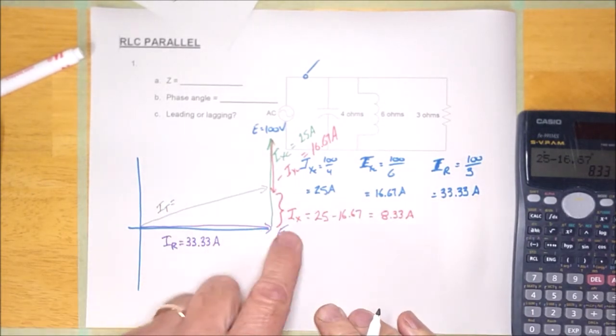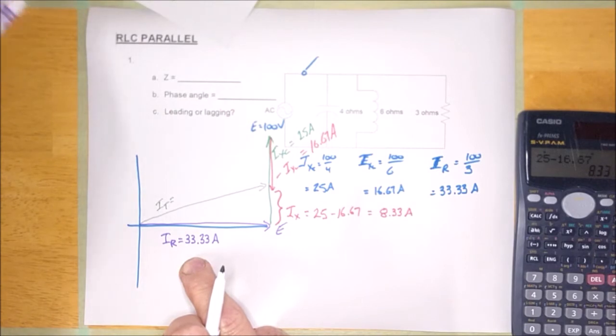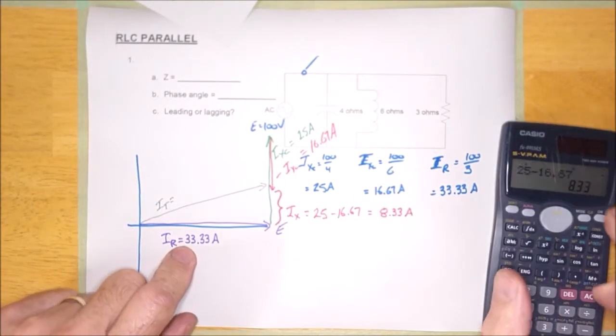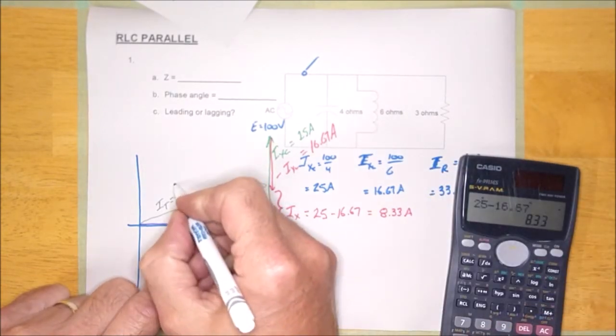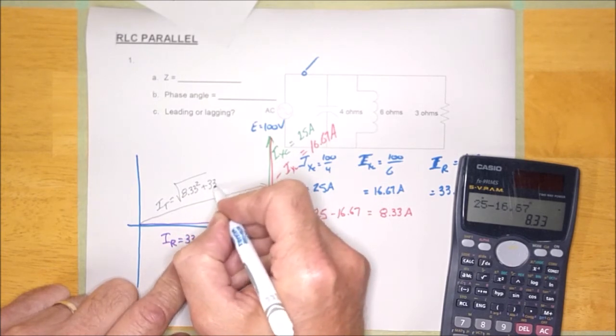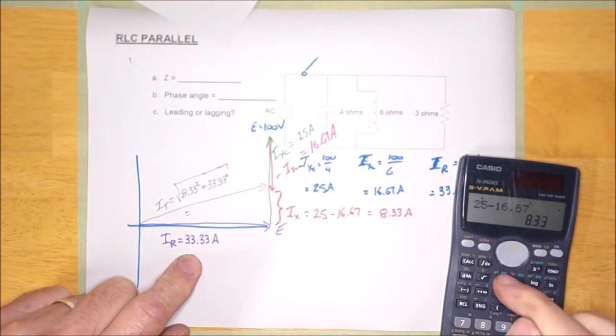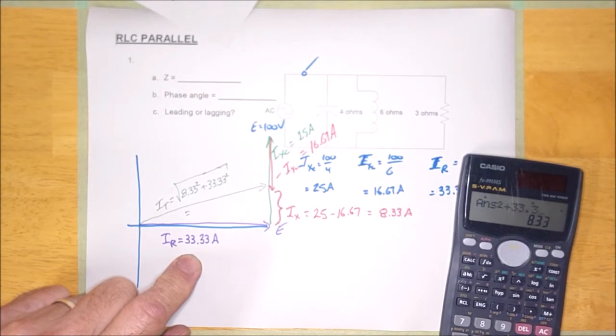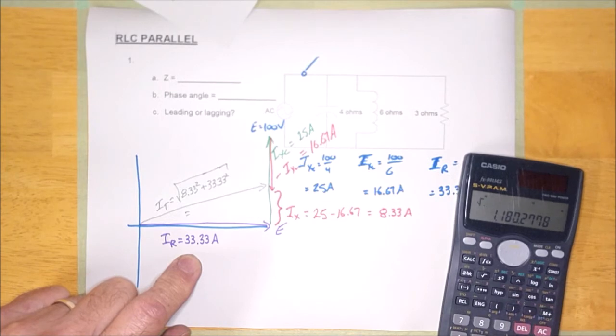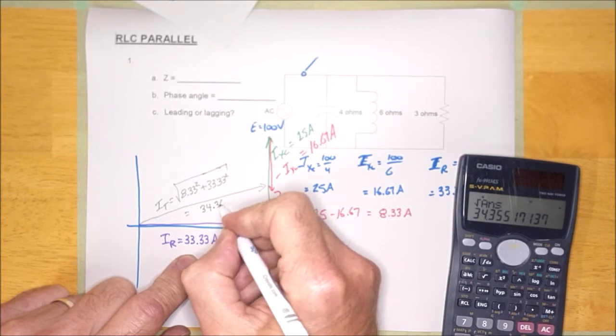And I can calculate our hypothetical I total. It is going to be 8.33 squared plus 33.33 squared. And that's because of the Pythagorean theorem, right guys? It's going to be 8.33 squared plus 33.33 squared. And so let's do that. 8.33 and hit squared here plus 33.33 squared equals root equals looks like it is 34.36 amps.